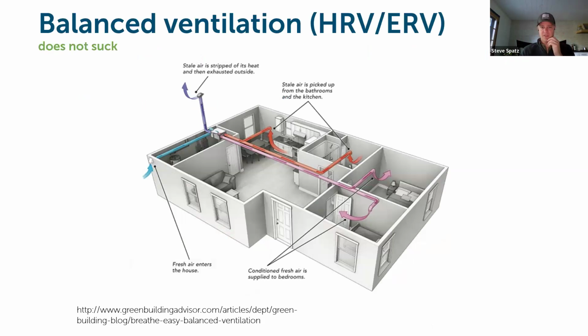So with a balanced system, you are providing equivalent fresh air directly from the outside into the home, moving through the HRV or ERV, where the exhaust stream of air that's pulling moisture-laden air and pollutant-laden air out of the house goes through the same piece of equipment, and those two air streams cross paths in the heat exchanger, and that's where the BTUs and/or humidity is exchanged into the incoming stream of fresh air. So you're getting conditioned air into the building. Different equipment available on the market has different filter options as well. So different MERV rated filters and even up to HEPA filtration as well.